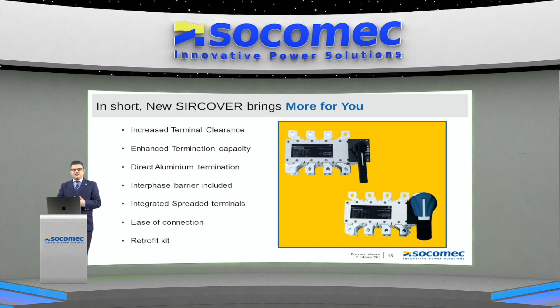Talking about IEC norms, the transfer switching is fully compliant with IEC 60947-6-1 class PC, the most specified standard worldwide. This differs from standard IEC 60947-3 because it's purpose-built for a safer transfer between two sources. For a single source, -3 sufficed, but for two sources the IEC committee innovated a new standard, with testing sequences including temperature rise and short circuit withstand at a more enhanced level than for isolators.